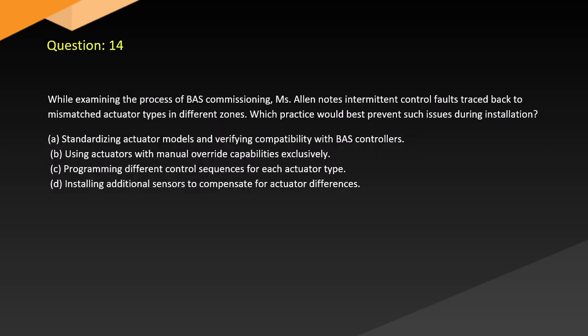Question 14. While examining the process of BAS commissioning, Allen notes intermittent control faults traced back to mismatched actuator types in different zones. Which practice would best prevent such issues during installation? A. Standardizing actuator models and verifying compatibility with BAS controllers. B. Using actuators with manual override capabilities exclusively. C. Programming different control sequences for each actuator type. D. Installing additional sensors to compensate for actuator differences.